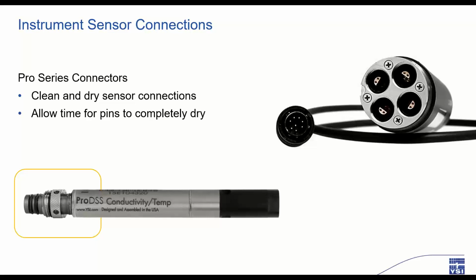The connectors or ports where the sensors are installed are just as important as the sensors themselves. Many of our instruments, like the ProDSS, require these connections to be clean and dry in order for their sensor to optimize its performance. Water, dirt, corrosion, or other foreign material found in these connections will likely cause interrupted signals and the collection of erroneous data. If the port or sensor connection appears dirty, flush them out with deionized or distilled water and then follow up with a rinse of isopropyl alcohol and a light blast of compressed air to help in the drying process.